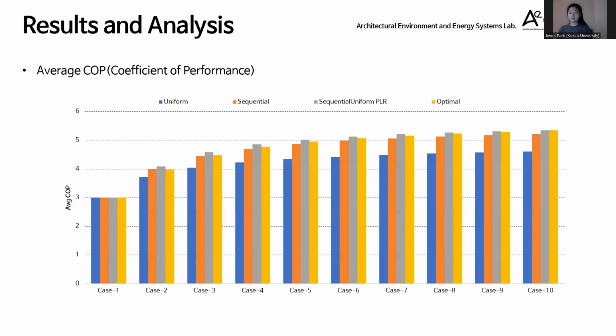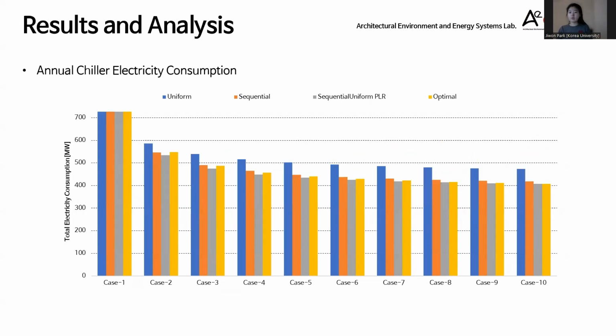Case 1 has an average COP of approximately 3.0, but as the number of chillers increases in all algorithms, the average COP gradually increases. Additionally, we found that the Sequential/Uniform PLR algorithm yielded the highest average COP in all cases. When examining the annual cooling load and cooling energy consumption for each case, it is observed that as the number of chillers increased in all algorithms, the cooling energy consumption decreased. It is also evident that the Sequential/Uniform PLR algorithm resulted in the lowest energy consumption among all cases.